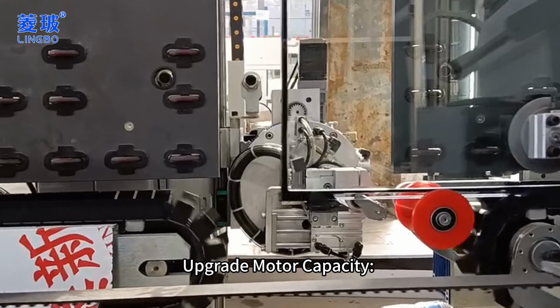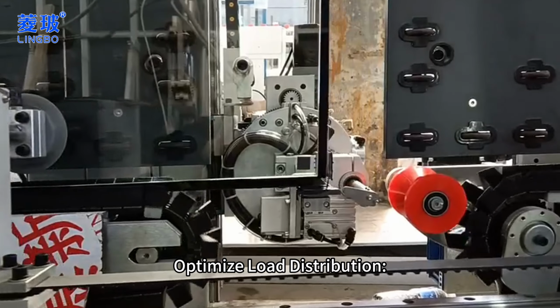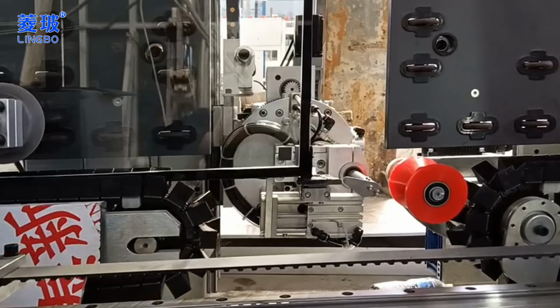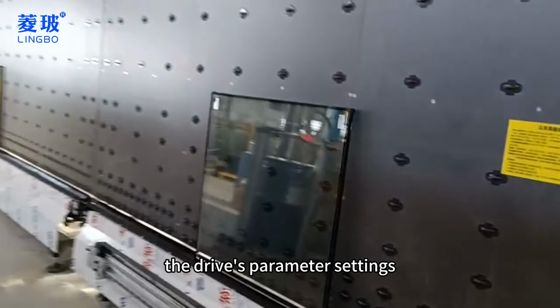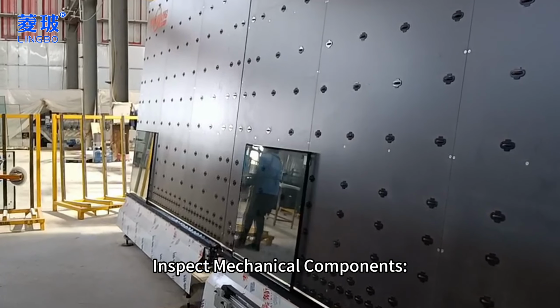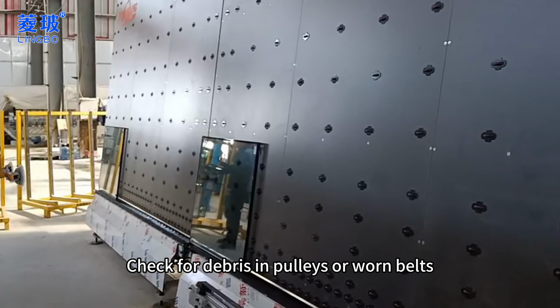Solutions. Upgrade motor capacity, replace with a higher torque motor. Optimize load distribution, adjust conveyor speed profiles via the drive's parameter settings. Inspect mechanical components, check for debris in pulleys or worn belts.